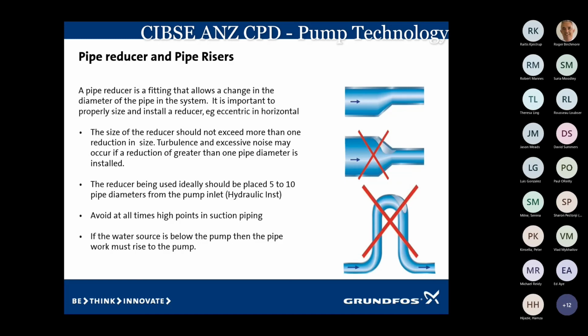Reducers, if it's a horizontal pipe running along into a pump, always use an eccentric reducer. That way, if there's any air in the water, any entrapped air, which there will be, it can actually pass through the pump and out again. If we use a concentric reducer in a horizontal pipe, then you've got a good chance that you're going to get entrapped air caught up. And if it's bad enough, if we lose our system pressure, then it'll accumulate, it'll cause noises, it'll starve the pump, and a number of other issues.